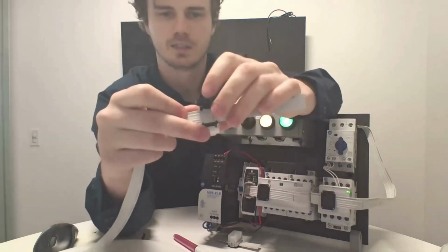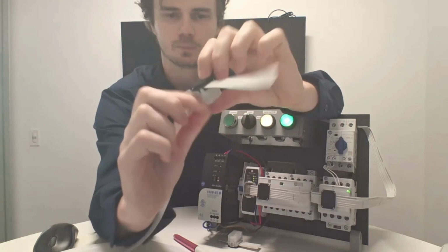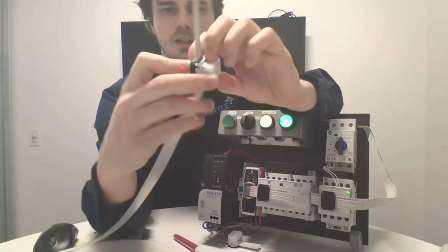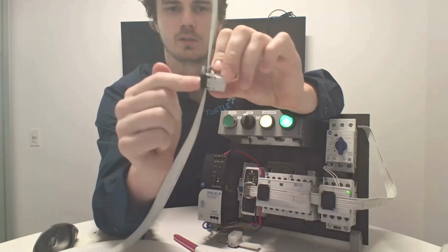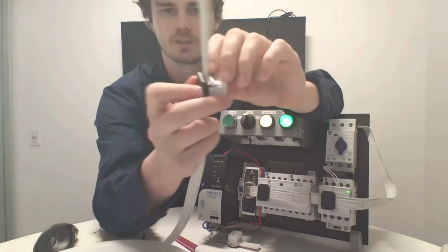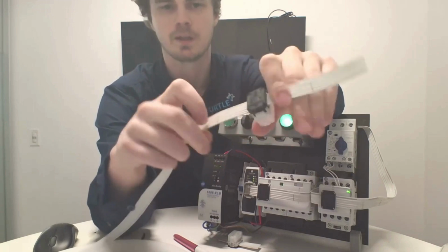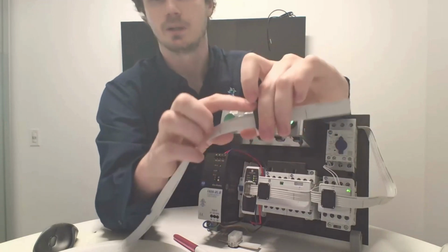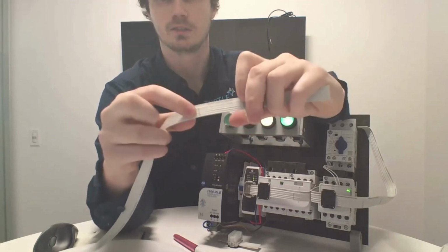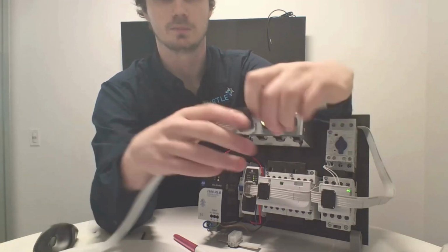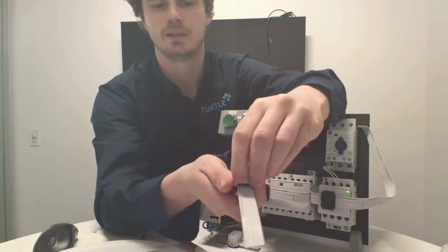And now it's latched in. You close this and clamp down with standard pliers. Once it's clamped down, it's going to bite in. These are single use, so if you clamp this down, I can't take it off and reuse it, so I'm not going to do that right now. And then if you want to put an extra node, you want to make sure it's at least this far apart, which is going to be about 50 millimeters for every single device. Once it's clamped down, you'll be able to pull off the back.